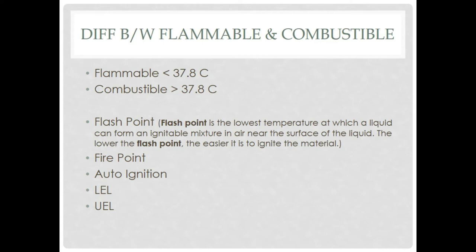To understand auto-ignition: as temperature rises, chemical vapors form. Those vapors reach the flash point. In the atmosphere there is oxygen. The fuel itself becomes vapor at a certain temperature — at the fire point. With direct sunlight or another heat source, the material can auto-ignite. The lower explosive limit (LEL) is the lowest concentration of vapor that will explode, and the upper explosive limit (UEL) is the highest concentration.